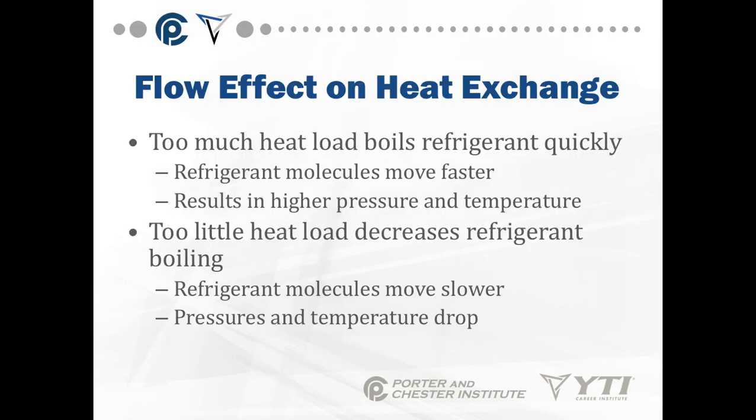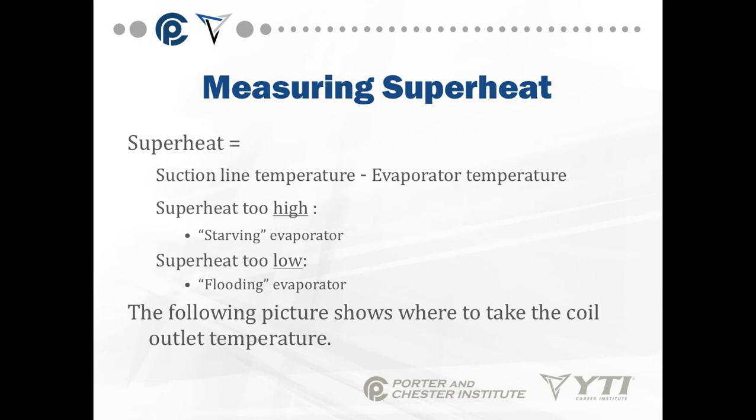Too much heat load boils the refrigerant away very quickly — refrigerant molecules move faster, resulting in higher pressure and temperature. Too little heat load decreases refrigerant boiling — refrigerant molecules move slower and pressure and temperatures drop. Superheat is the difference between the suction line temperature and the evaporator temperature. Superheat too high means a starving evaporator; superheat too low means a flooding evaporator.